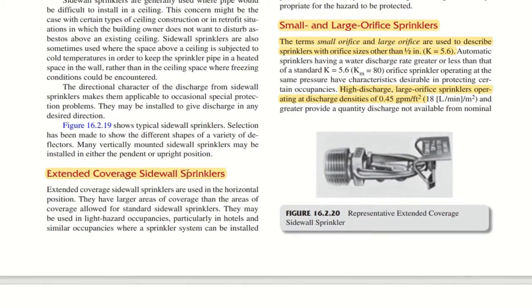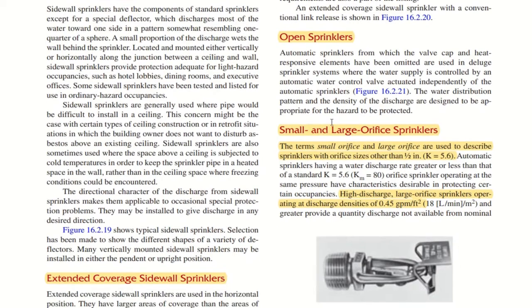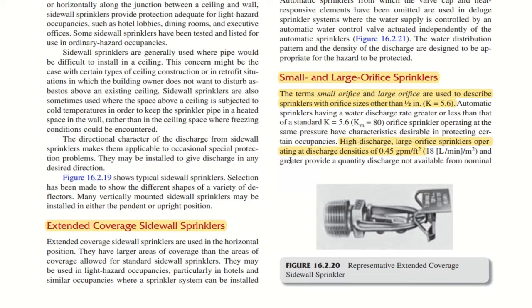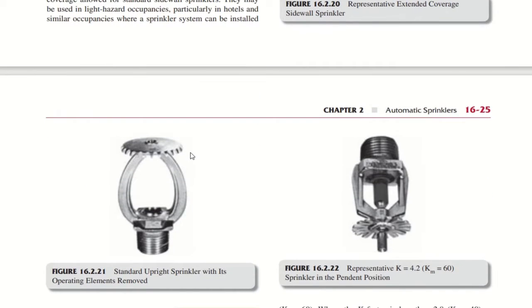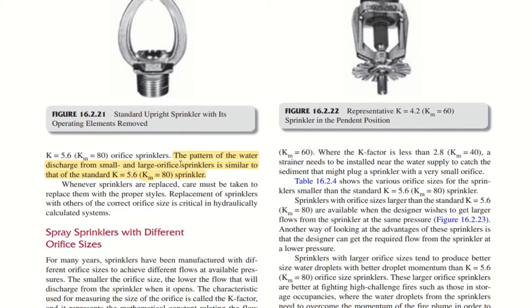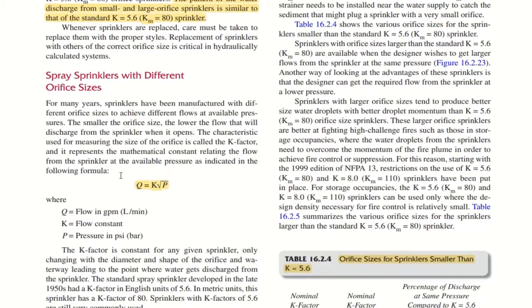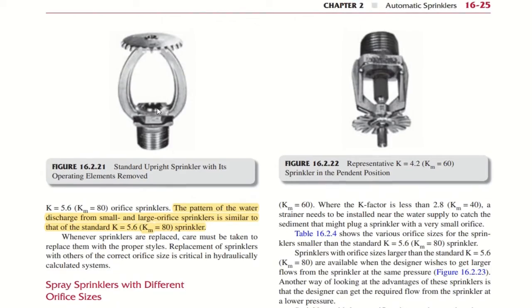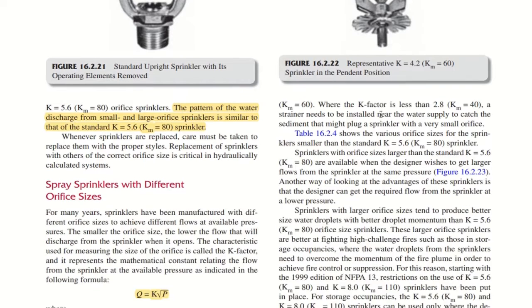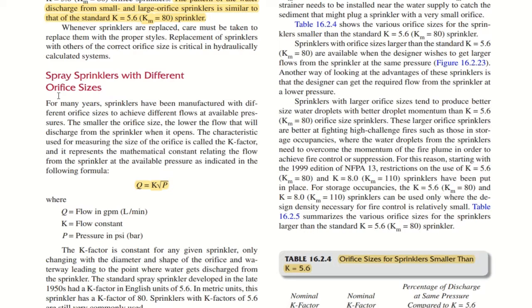Side wall sprinklers, you have extended coverage side wall sprinklers, open sprinklers, small and large orifice sprinklers. The terms small orifice and large orifice are used to describe sprinklers with orifice sizes other than half inch. So this is a very important point. And high discharge large orifice sprinklers operating at discharge densities of 0.45 GPM per square feet. This you need to remember. The pattern of the water discharge from small and large orifice sprinklers is similar to that of standard sprinklers with K factor 5.6. Here you can see this is an upright sprinkler, and the operating element is removed here. The pendant sprinkler with a bulb operating element. Here, spray patterns of spray sprinklers with different orifice sizes.